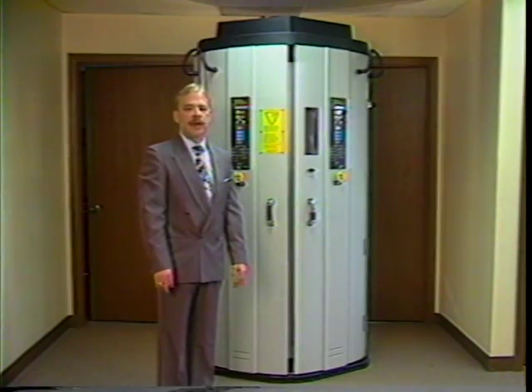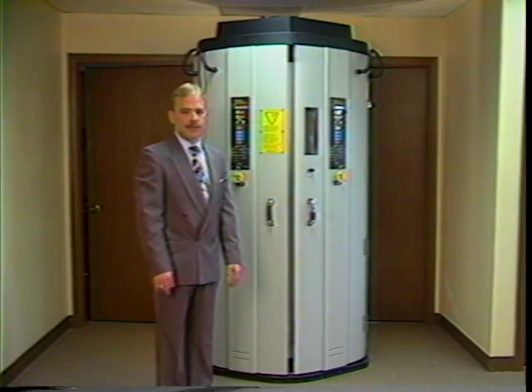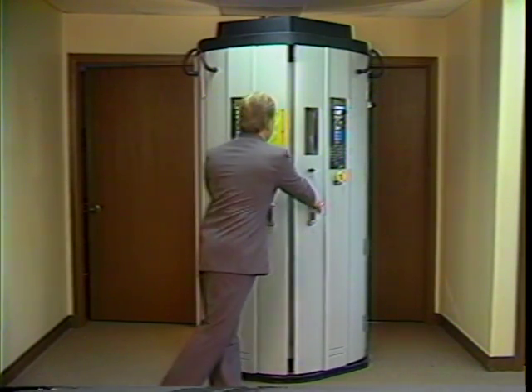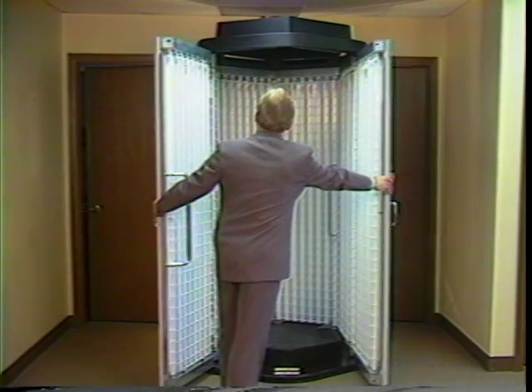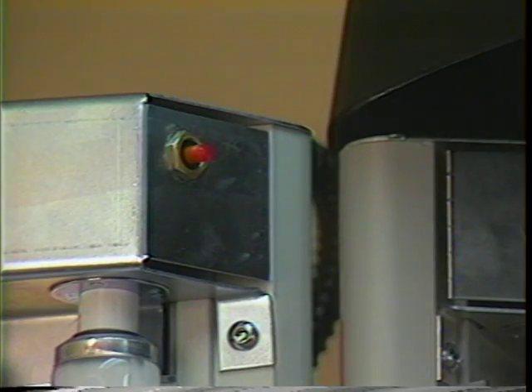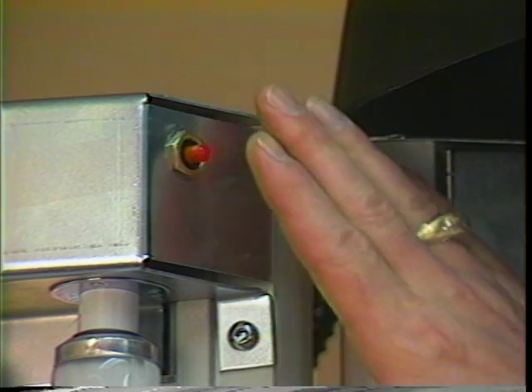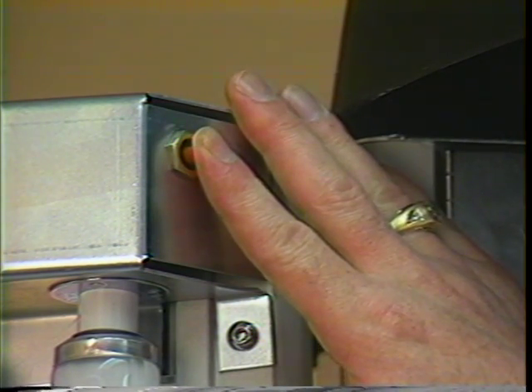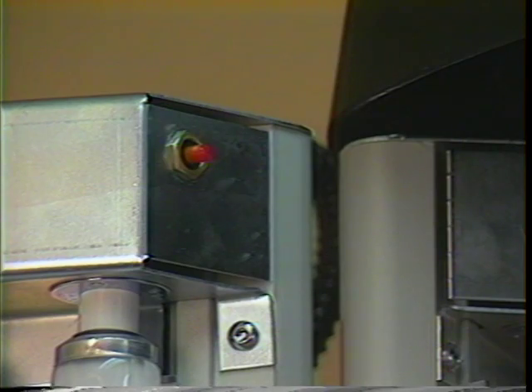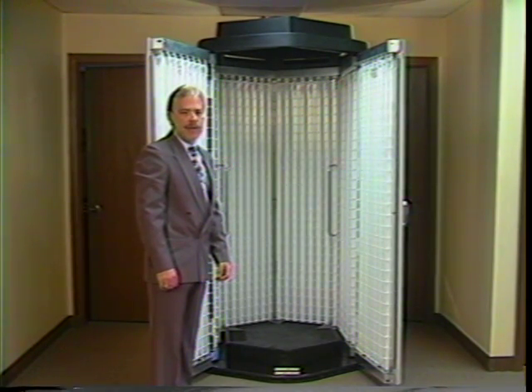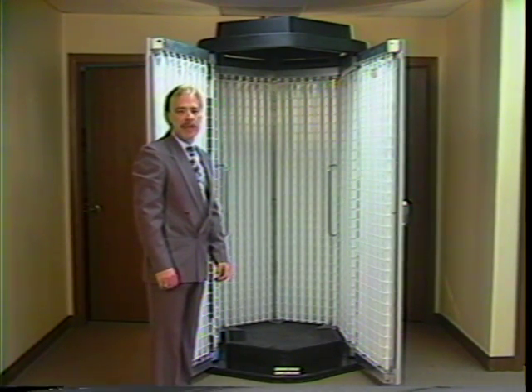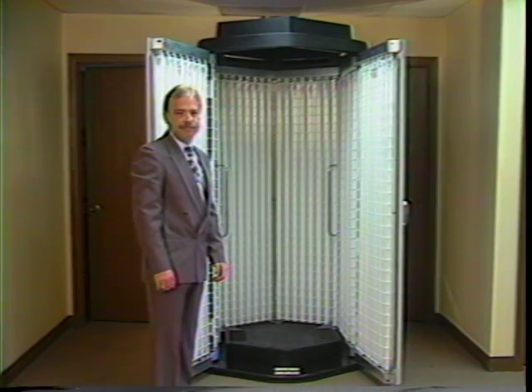Another unique design and safety feature of the HOUVA II system is the automatic door interlocking safety switch. When the doors are open more than 2 inches during any time for treatment, the lamps will automatically shut off and the timers will stop counting down. This prevents unnecessary UV exposure to the operator and makes recalculation of the remaining treatment time unnecessary.